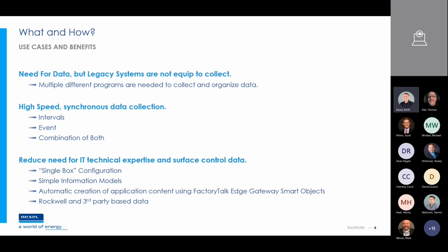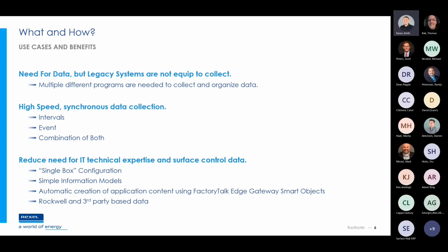Or it can be triggered, so there's actually an event-driven option to trigger data, which allows you to collect, let's say there's an AOI in the control system. You can enable a bit on that to trigger the event to log the data to the system. You can control the on and off state of the data collection bit in the ladder logic. So your trigger can be as simple as perhaps turning on that bit every time there's an alarm, to writing various complex ladder logic that considers multiple inputs to decide when to collect the data. And what I mean by that is you can get very creative on how and when you can trigger events and data into your system up to the IT space.